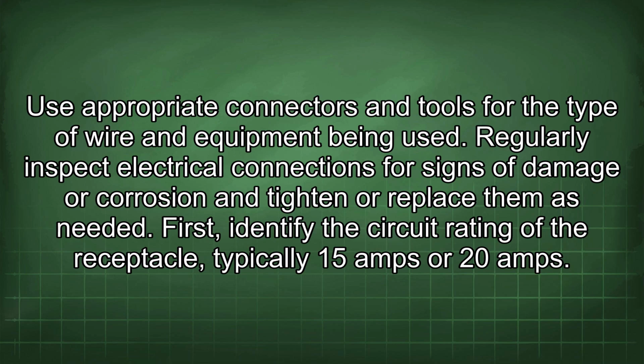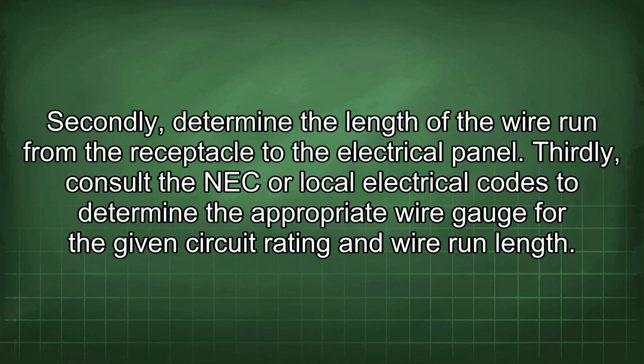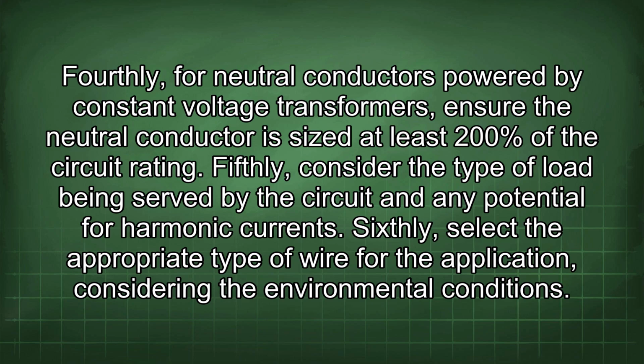First, identify the circuit rating of the receptacle, typically 15 amps or 20 amps. Secondly, determine the length of the wire run from the receptacle to the electrical panel. Thirdly, consult the NEC or local electrical codes to determine the appropriate wire gauge for the given circuit rating and wire run length. Fourthly, for neutral conductors powered by constant voltage transformers, ensure the neutral conductor is sized at least 200% of the circuit rating.